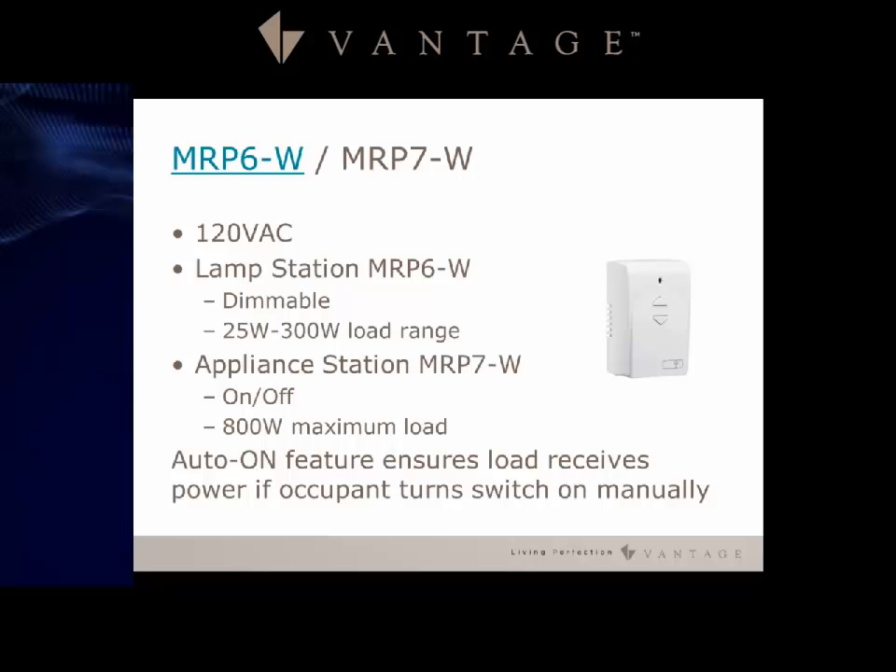The MRP6W and MRP7W are plug-in modules. The MRP6W is the lamp station with a single outlet, a 25 watt minimum and 300 watt maximum. The MRP7W appliance station has an 800 watt maximum and includes the same auto-on feature as the Accent Point 2, ensuring the load receives power if the occupant turns the switch on manually.